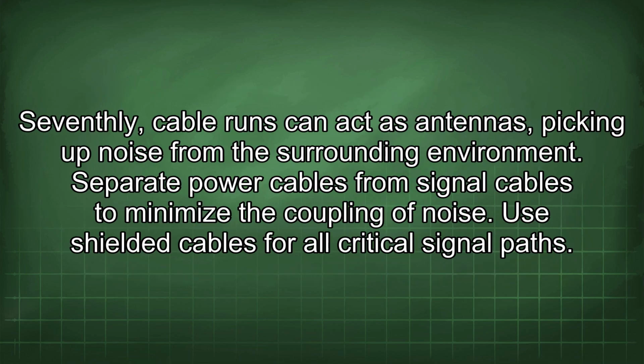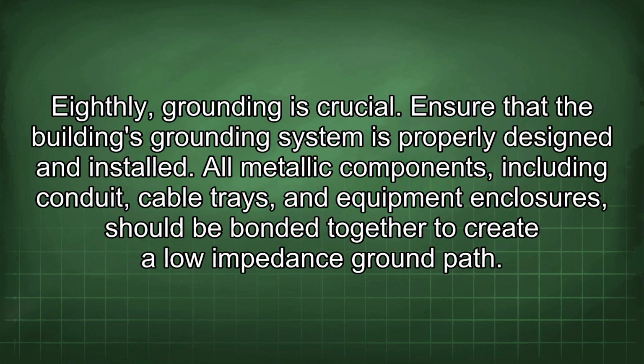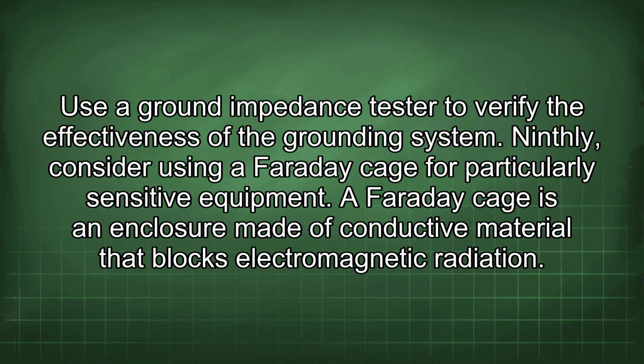Seventhly, cable runs can act as antennas, picking up noise from the surrounding environment. Separate power cables from signal cables to minimize the coupling of noise. Use shielded cables for all critical signal paths. Eighthly, grounding is crucial. Ensure that the building's grounding system is properly designed and installed. All metallic components, including conduit, cable trays, and equipment enclosures, should be bonded together to create a low-impedance ground path. Use a ground impedance tester to verify the effectiveness of the grounding system.